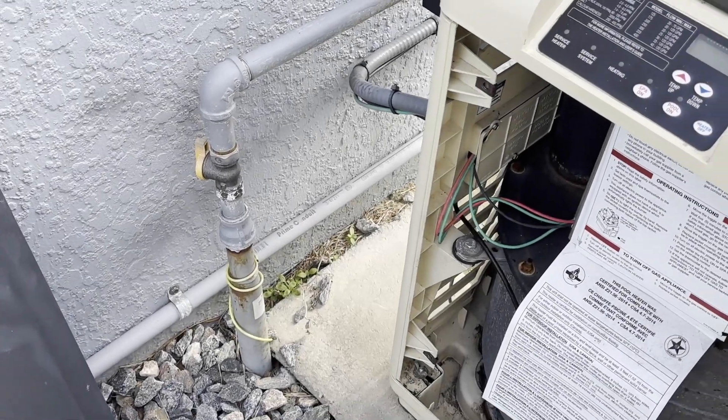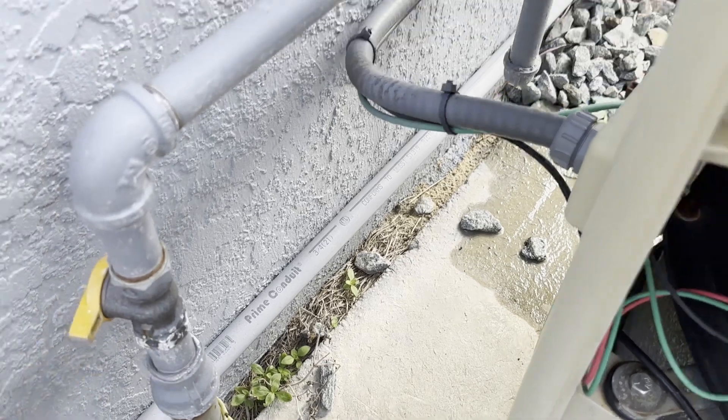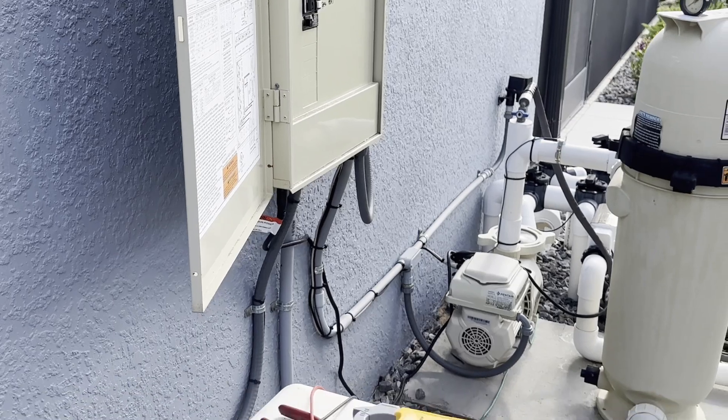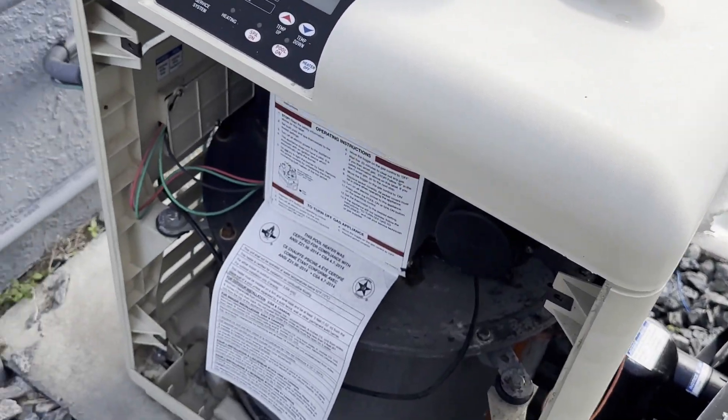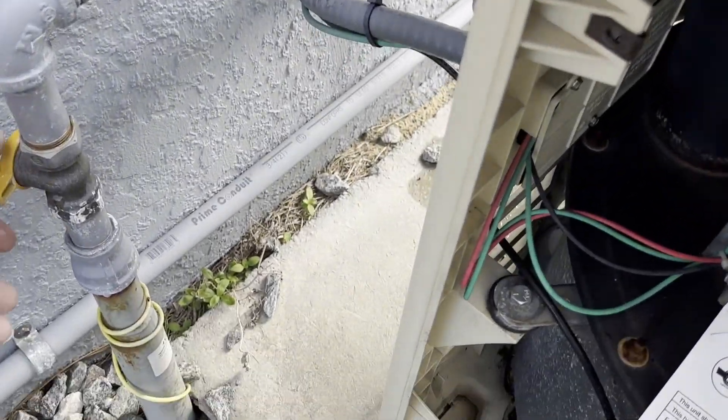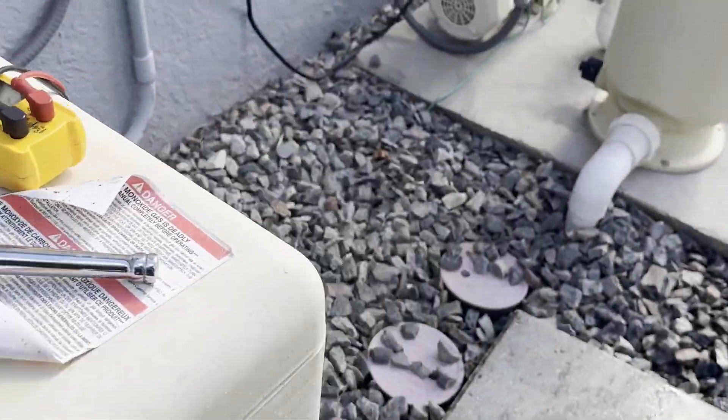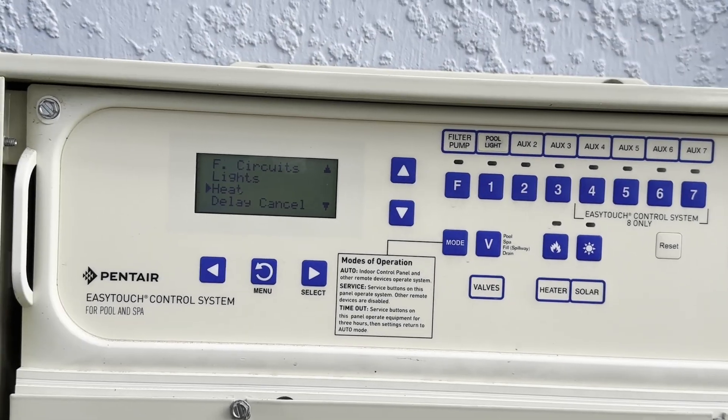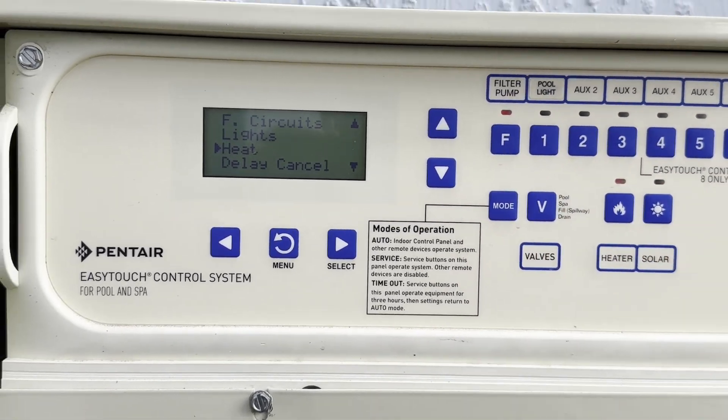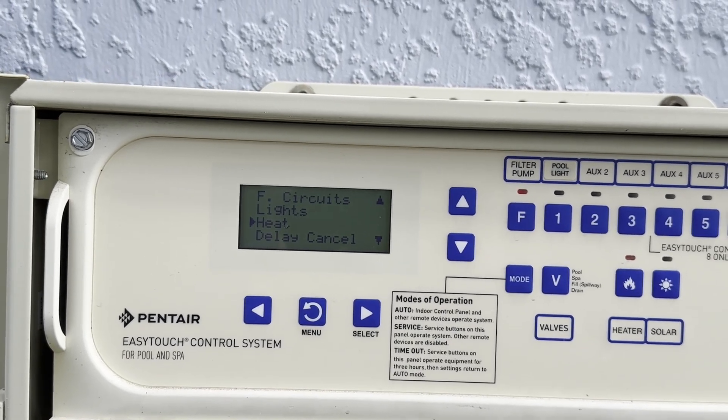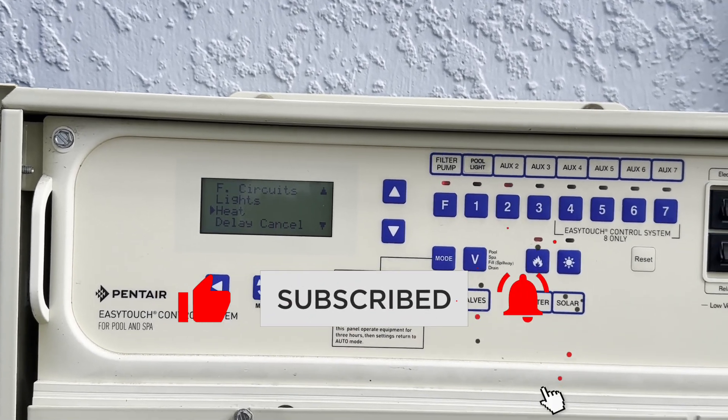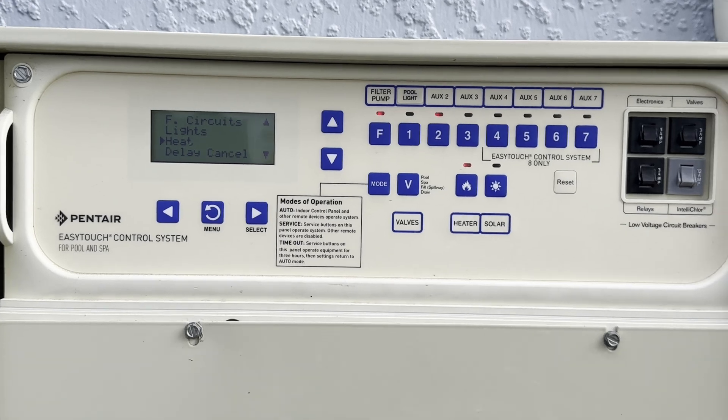So before we remove the sensor, you want to turn the gas off and you want to turn the pump off. So make sure that there's no water flowing through it. You will get some water coming out when you remove the gas sensor, but it shouldn't be that much. We go back and we will turn our gas back on and we will go to our pump and we'll turn our pump back on. And there goes the pump.